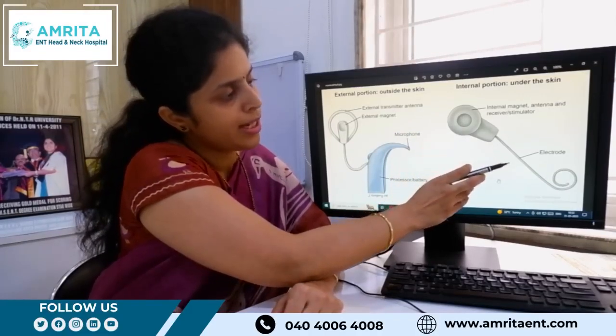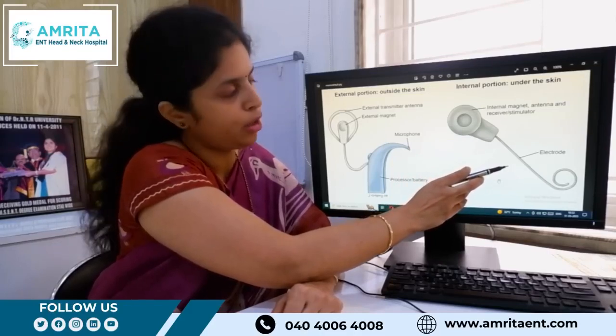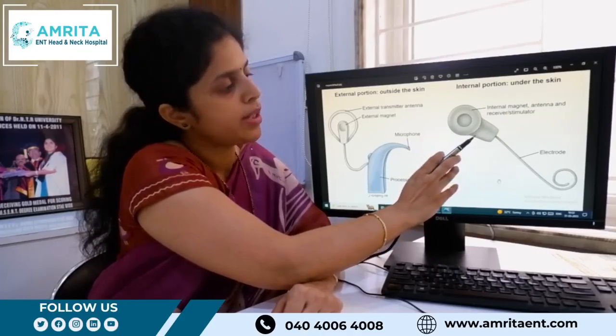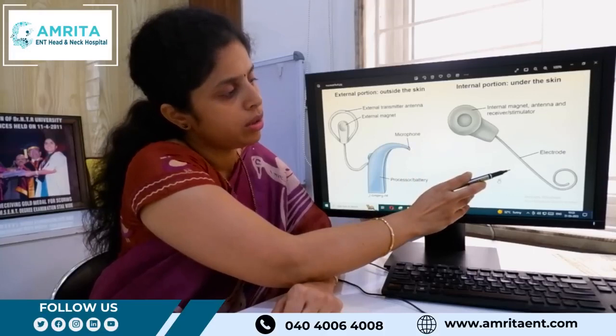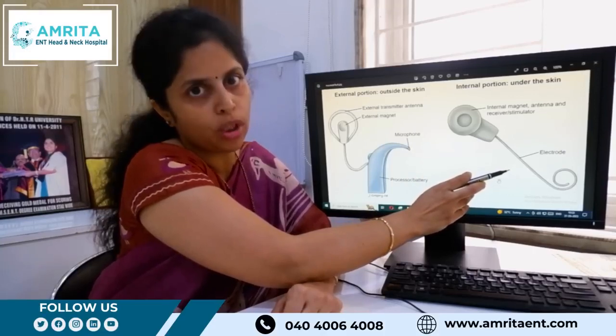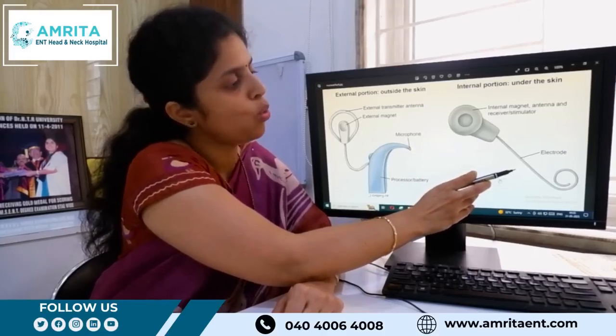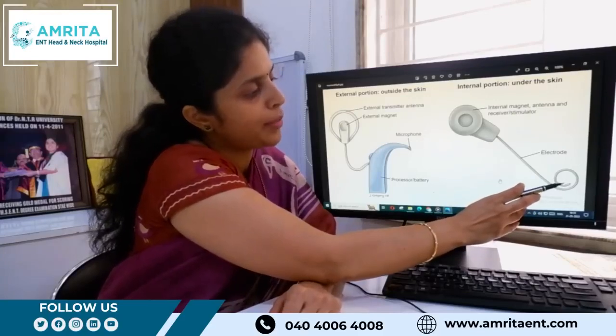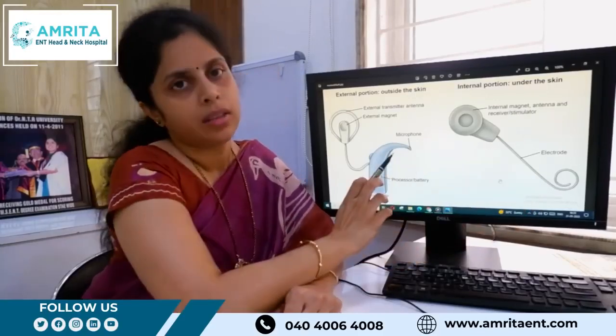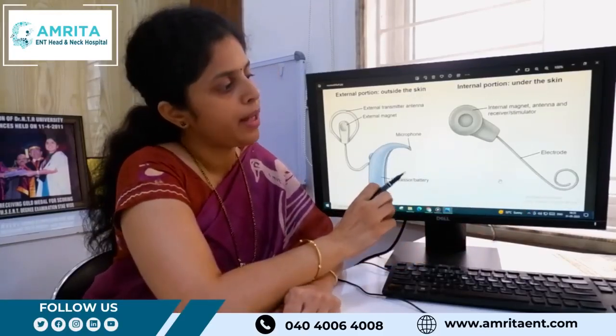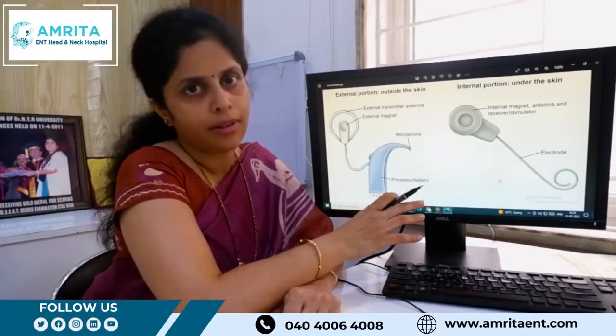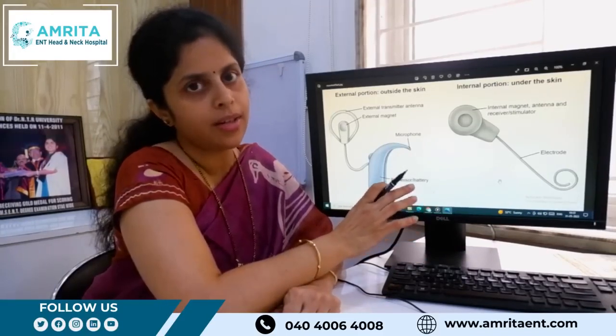The receiver or stimulator, once it gets the digital signal, depending on the frequency, transmits it to that particular electrode. That is, the high frequency sounds go to the electrode in the basal turn of the cochlea, and the low frequency sounds go to the electrode in the apical turn of the cochlea. These signals are picked up by the cochlear nerve and it is perceived as hearing by the brain.